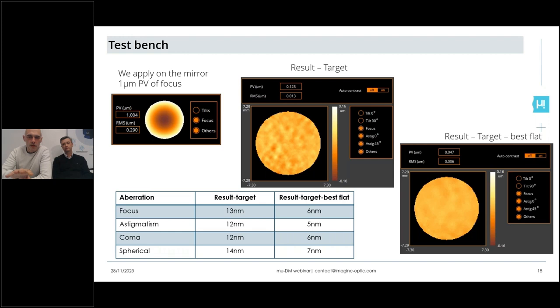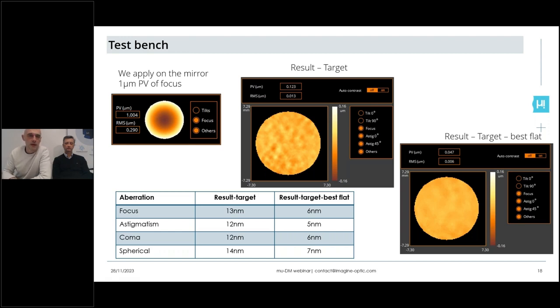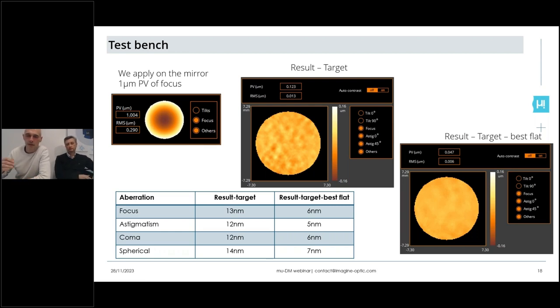Here is an example showing open-loop operation: the benefit of having very good linearity will be repeated during the hands-on. If you apply, for example, one micron peak-to-valley of focus on the circular pupil of the mirror and ask the mirror to achieve this value, the residual wavefront is only 13 nanometers RMS. This shows that the mirror nearly perfectly achieves the desired shape with a very limited amount of residual aberration, well below the diffraction limit. This was demonstrated for the main third-order aberrations typically seen in microscopy and ophthalmology.